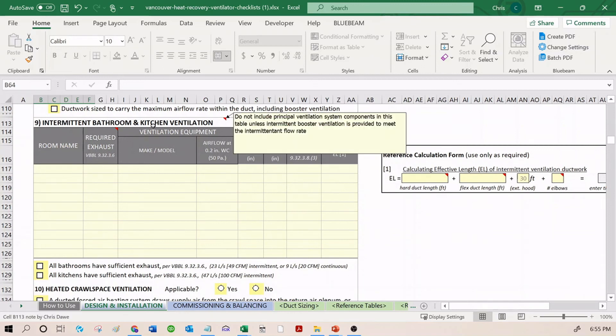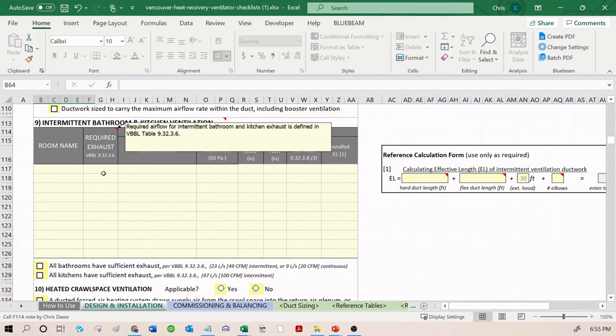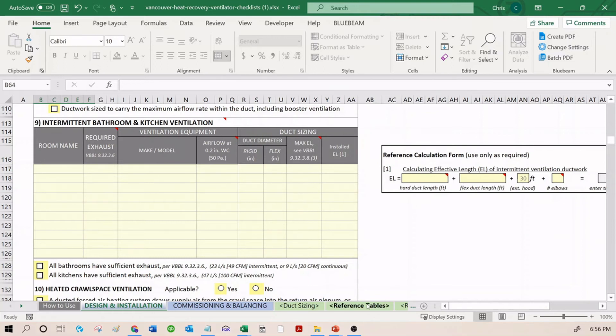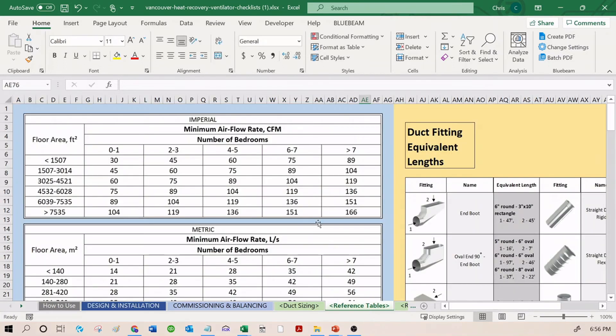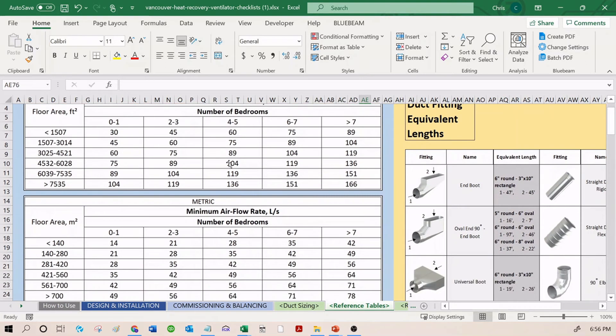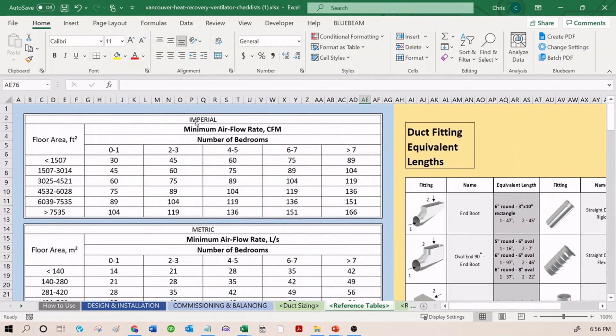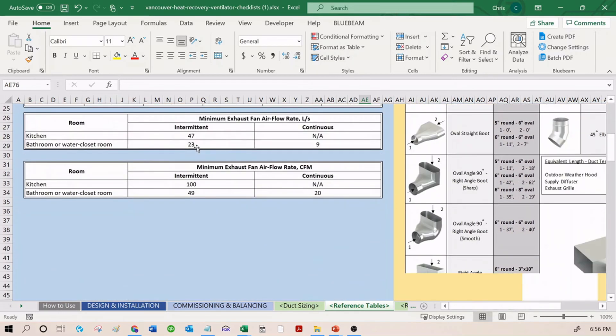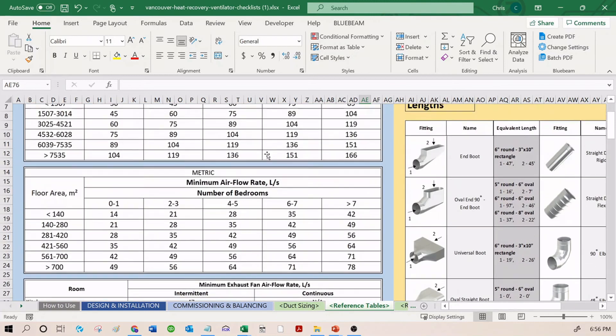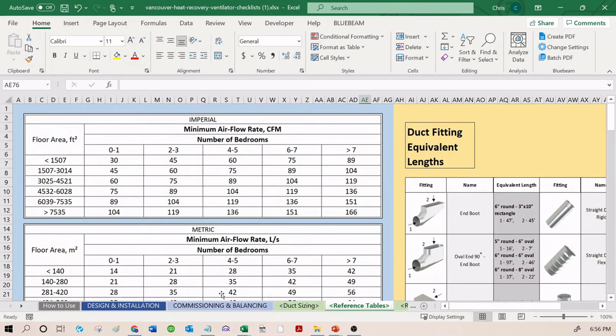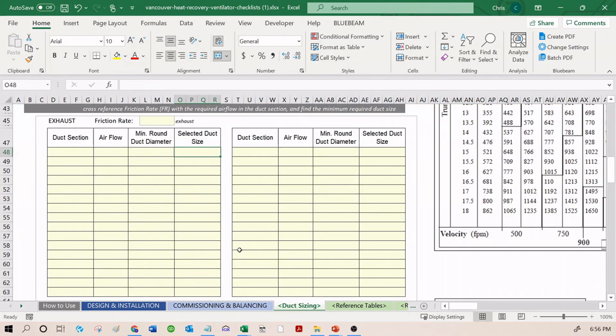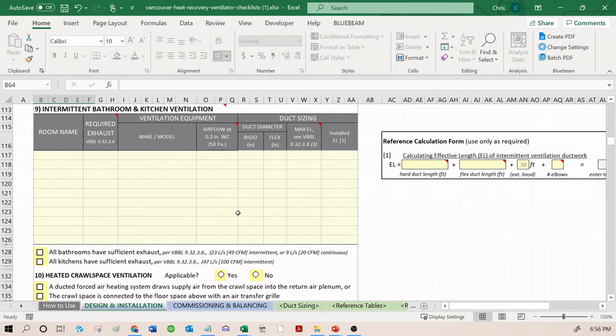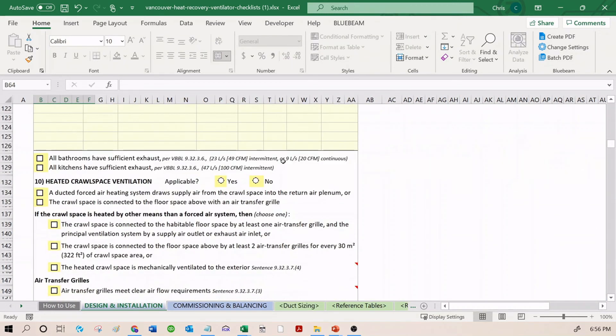Section 9 is intermittent bathroom and kitchen ventilation. These have different requirements. There are individual building code tables, Vancouver Building Bylaw tables, that govern the minimum duct size for these. If you go to reference tables, you're going to see right here the Vancouver Building Bylaw tables in Imperial and Metric. This is for required airflow, depending on your building size and number of bedrooms. We also have airflow rates in kitchen and bathrooms. This table should be completed as well. And then, similar to above, all bathrooms have sufficient exhaust, all kitchens have sufficient exhaust.